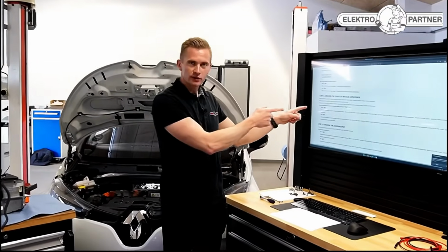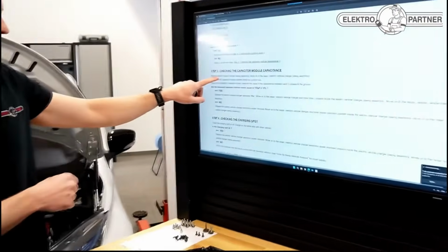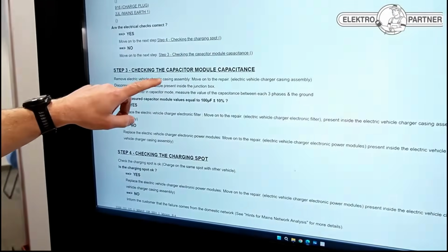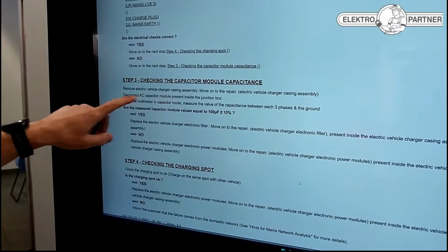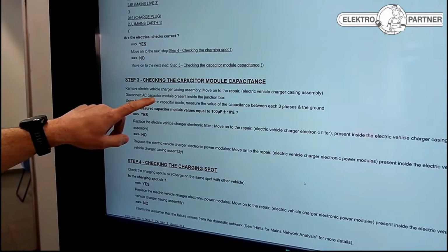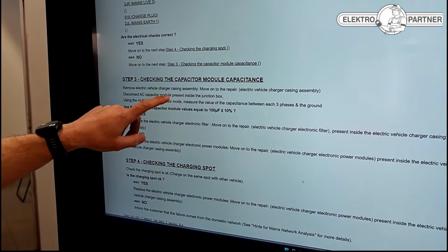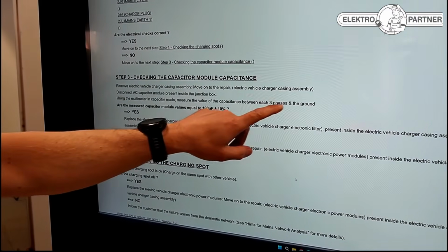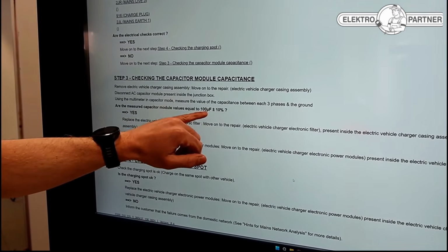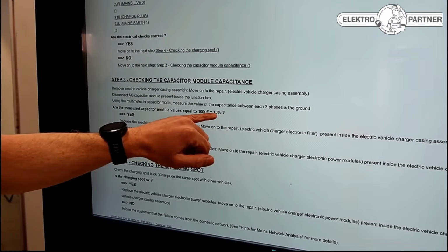If we just go back to the manufacturer's instructions here, the next step is simply to remove the electric vehicle charger casing assembly, and then we need to disconnect this AC capacitor module, and we need to measure it in relation to each phase and ground, and we should get a value of around 100 microfarads plus or minus 10%.